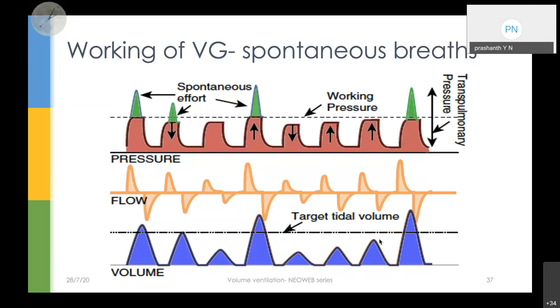But here the ventilator gets a little confused, and to achieve the normal target tidal volume, it will take some time. Suppose here the baby, after the spontaneous effort, has stopped breathing, and then the ventilator takes over. To achieve the target tidal volume, it is taking some time. If you can see, the baby's contribution is not there in the next one, so your volume is less. The ventilator has realized it, and it is slowly increasing the pressure to make sure the volume is also increasing. So this is how Draeger and most of the other ventilators work with spontaneous breaths.